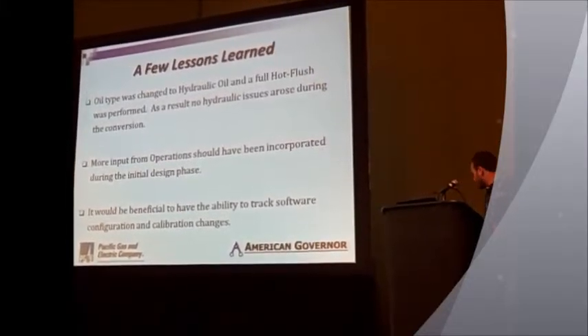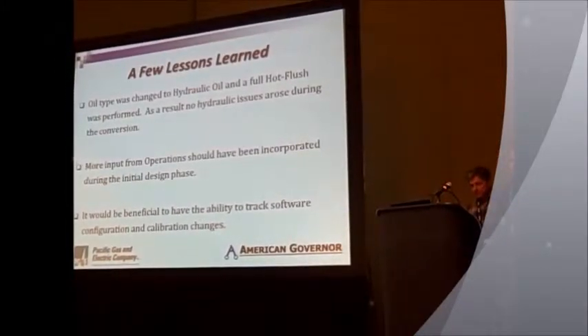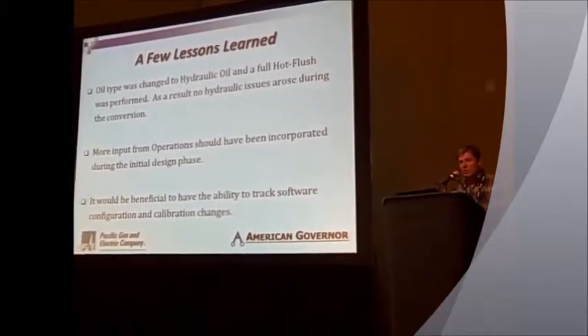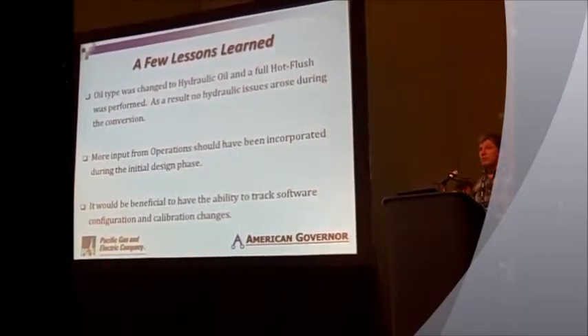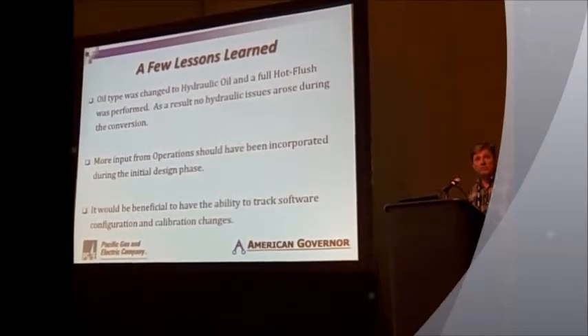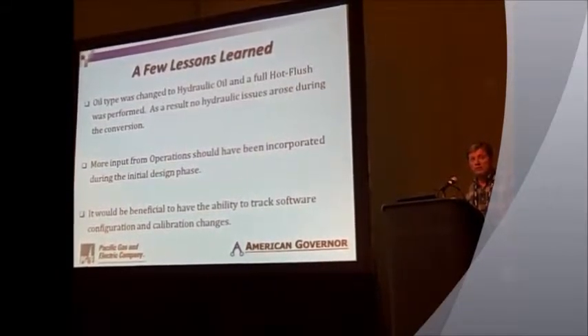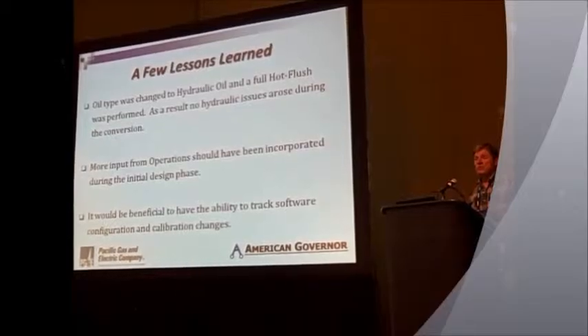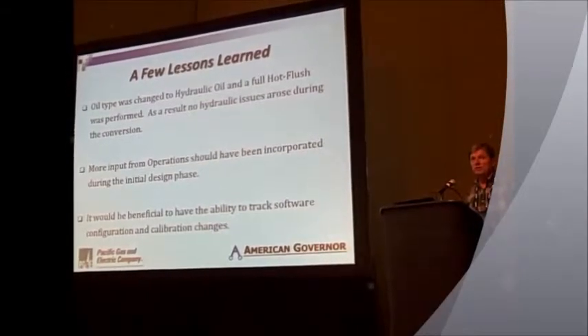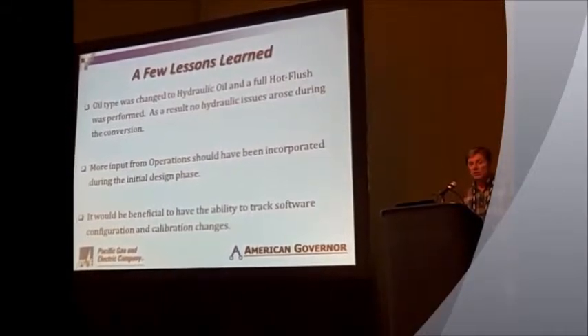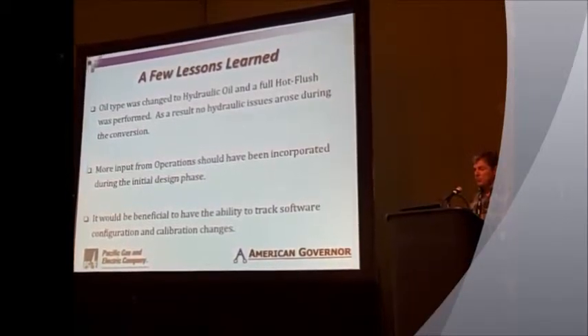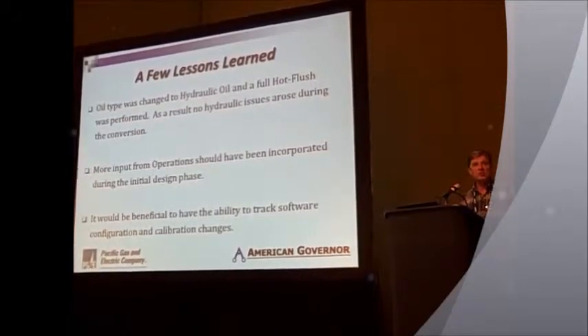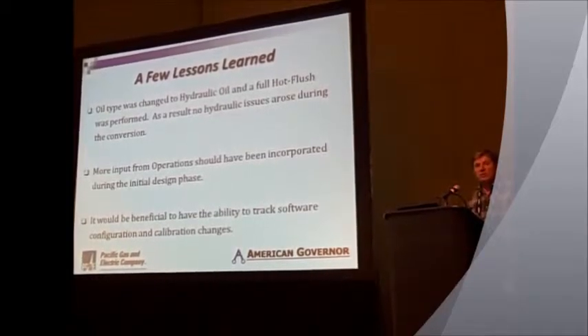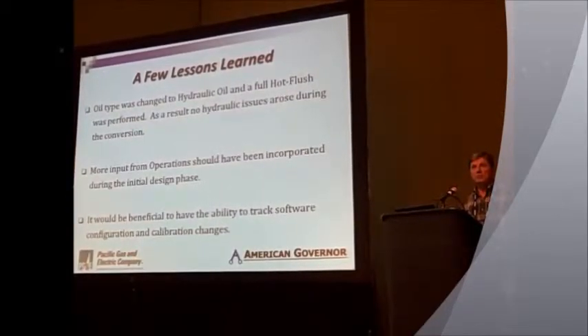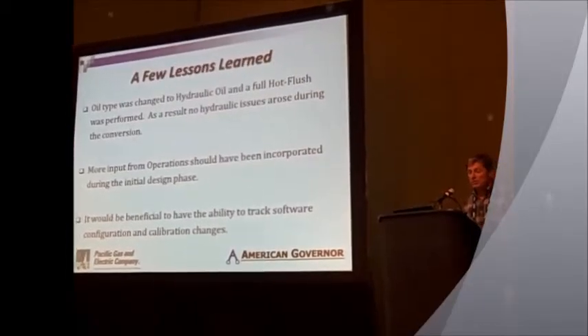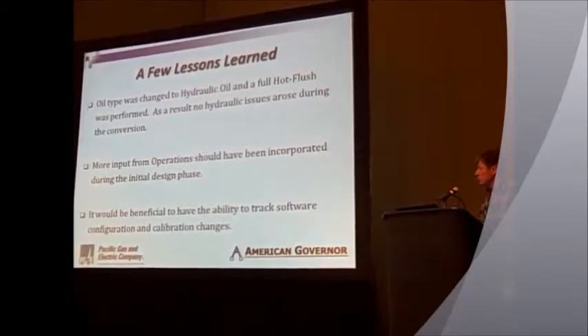I'm going to invite Mark back up real quick to talk about some of the lessons learned with this project. One of the things on this: the old governor used GST 68 turbine oil, and the recommendation was made that we should switch to hydraulic oil because of the tighter tolerances of the new control valves. We also performed a hot flush on the entire system. As a result of that, we did not have a single hydraulic related problem during commissioning and haven't since. So that was a strong benefit.